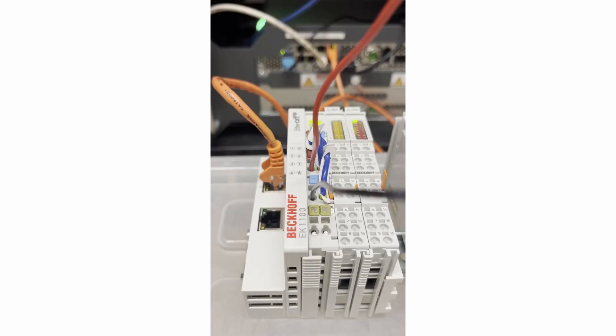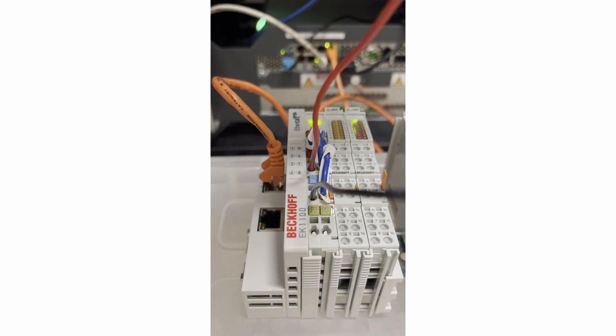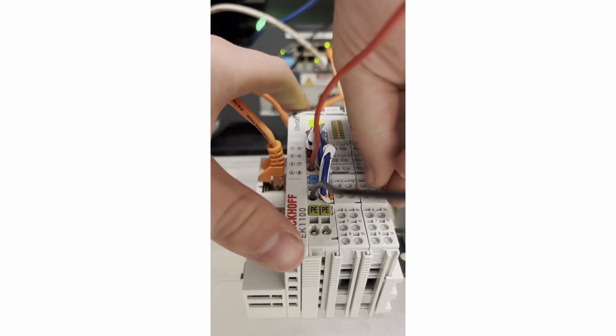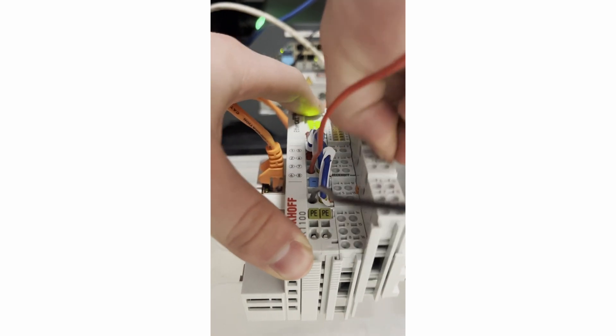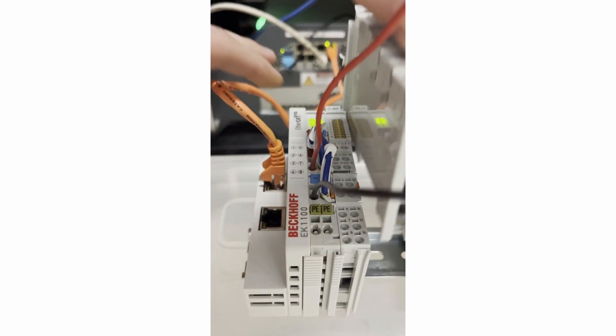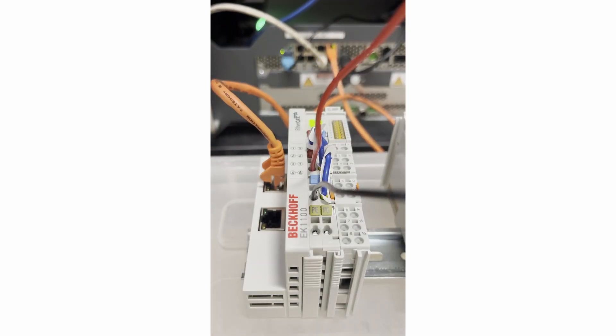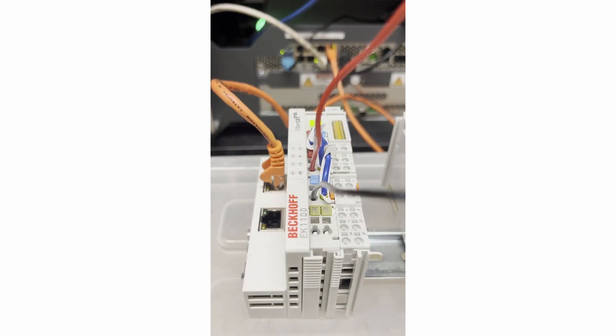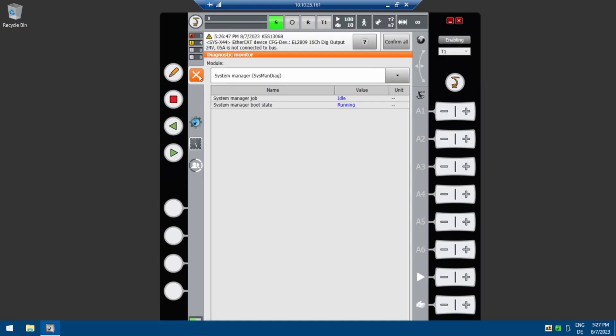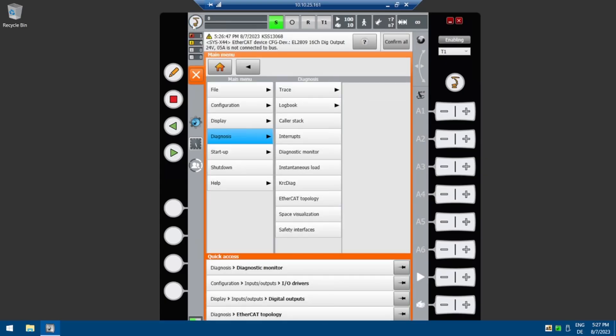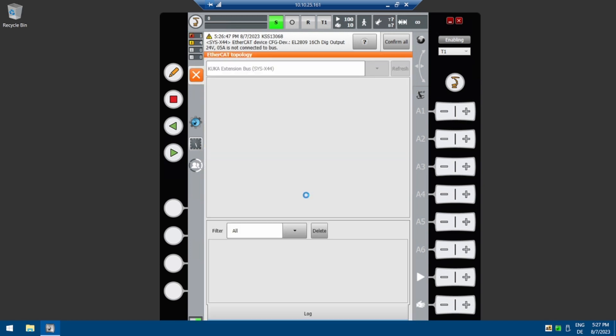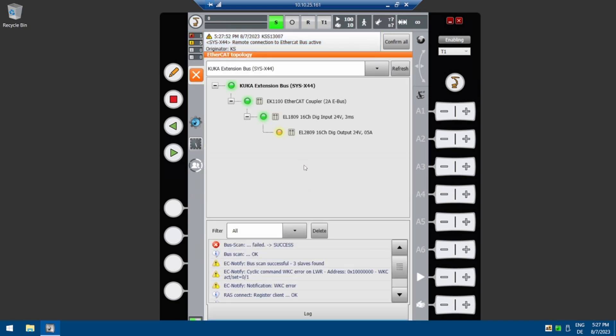If the EL2809 becomes disconnected from the extension bus, the drives will stay enabled and no error message or warning is displayed on the SmartPad. You can check the status of the extension bus by selecting Menu, Diagnosis, EtherCAT Topology, Extension Bus. This is helpful for seeing the status of the extension bus.